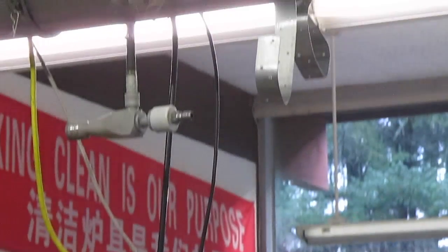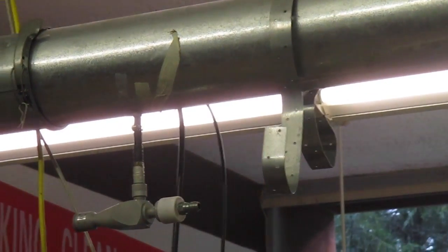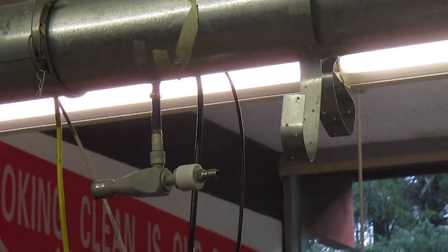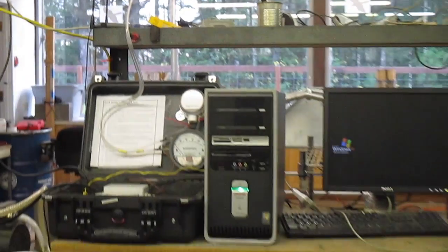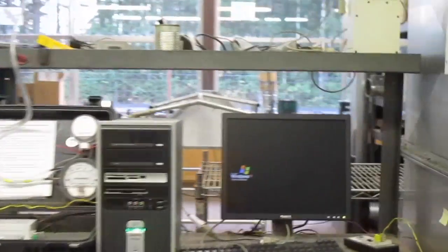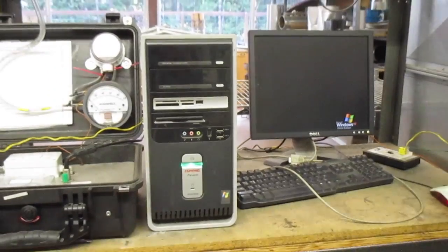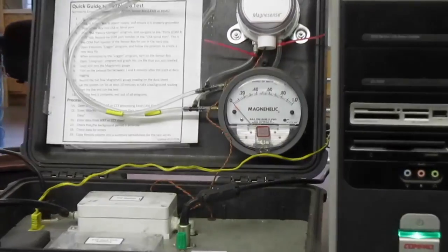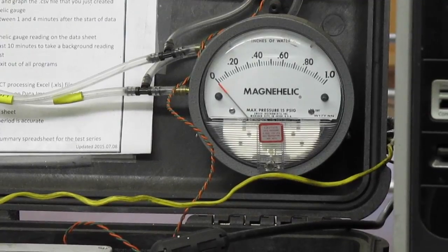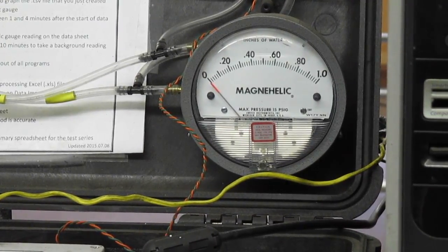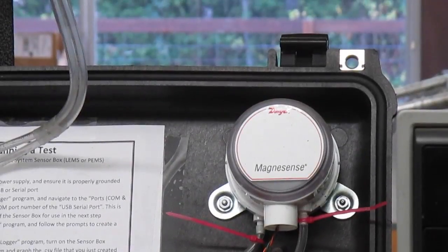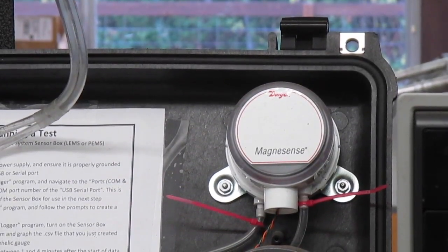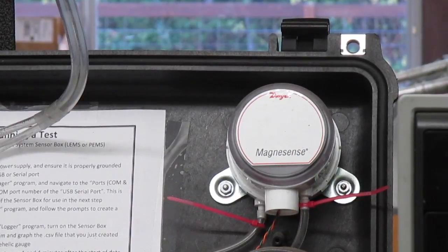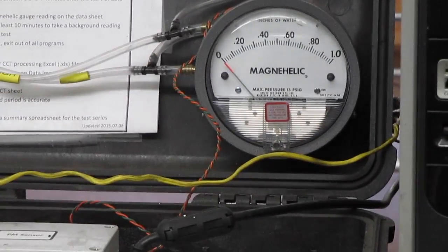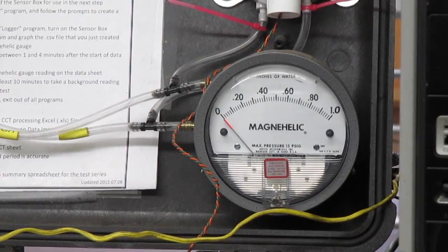See that thick black line is a sample tube. Gravimetric sample goes on the left. No filter in place there. So here we have the Magnehelic gauge. The Magnehelic gauge is used to calibrate MagneSense, which is the digital pressure transducer. You need to measure pressure in the duct, dynamic pressure in the duct, to figure out the flow rate.